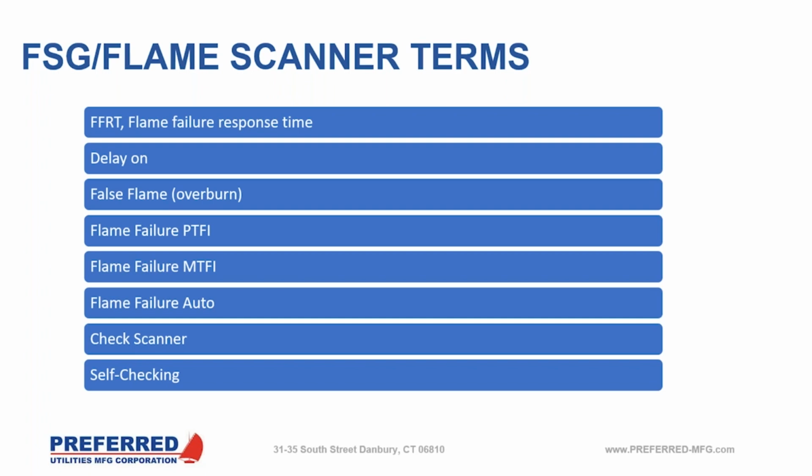In the industry, on most boiler applications, you're going to see this FFRT is going to be around a 3-second time period.